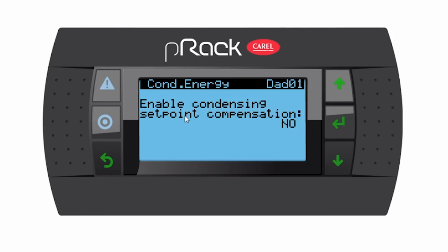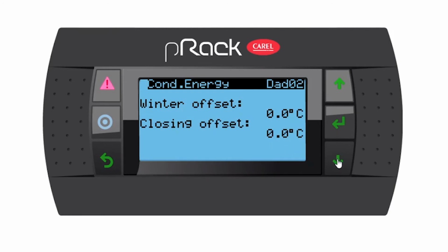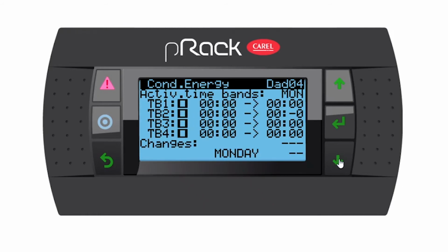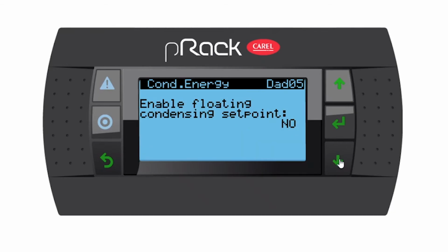Enable condensing set point compensation, no. You have some offsets. If you do say yes on the compensation, here's some set points. You have some time bands. But this is the one. Enable floating condensing set point. I'm going to say yes.